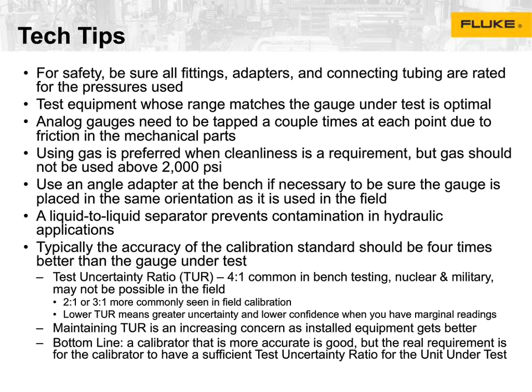We talked a little bit about matching the test range to the equipment before. So basically, if you're working at 1,500 pounds, try to get a test calibrator or a gauge or whatever you're going to use to be as close to 1,500 pounds as possible. That'll give you the best accuracy. Analog gauges, this is a big difference between analog and digital. With an analog gauge, you've got to tap it a couple of times because you've got mechanical parts that need to move. You've got a little bit of hysteresis error, friction and other forms that cause the gauge to stick, and you just have to give it that little tap in order to clear that.